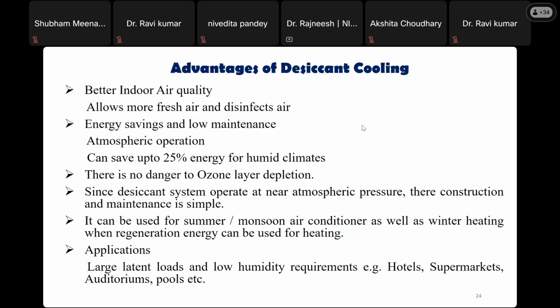So the processes that we have discussed on the psychrometric chart are applicable to both the solid as well as the liquid desiccants. So, energy saving and low maintenance: as I mentioned, they are operated with the help of low grade energy, that is heat energy. Heat energy is required to regenerate, and though some pumping is required, the pumping requirement is very less as compared to the conventional air conditioning system. So they can save up to 25% energy for humid climates. There is no danger of ozone layer depletion since we are not using any CFCs or HCFCs or any other commercial refrigerants in the system. We are simply using the desiccant solution, which has no impact on the ozone.